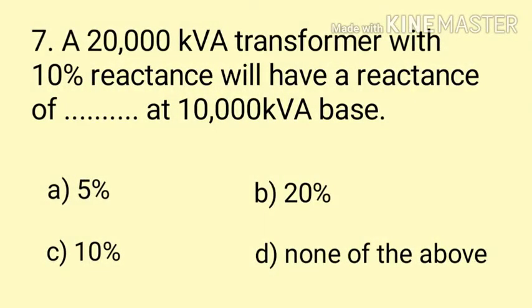Question number 7. A 20,000 KVA transformer with 10% reactance will have a reactance of dash at 10,000 KVA base. Is type ka question maine abhi abhi kiya hai. Isme hume nikalna hai reactance — formula put karo base KVA par: (base KVA / rated KVA) × percentage reactance at rated KVA = (10,000 / 20,000) × 10% = 5%. The correct answer is Option A.